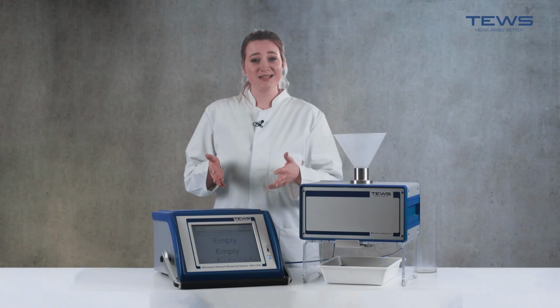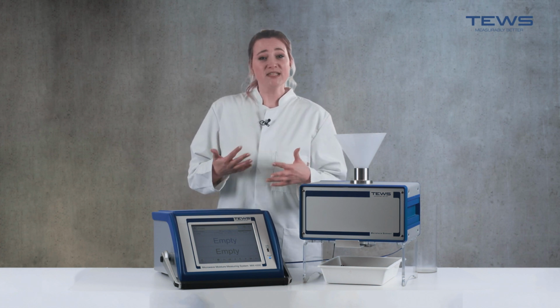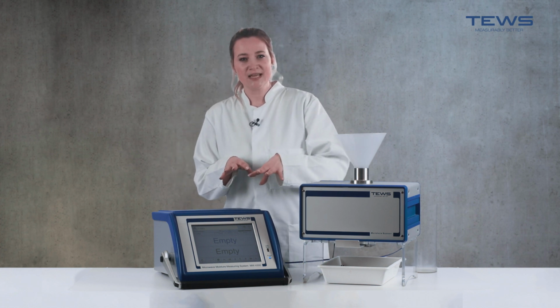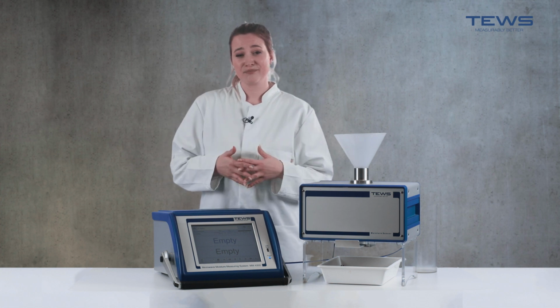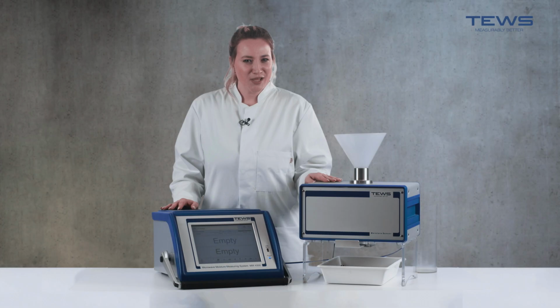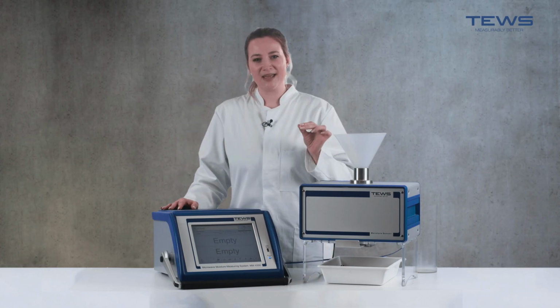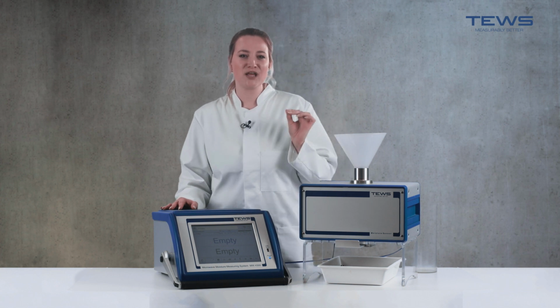We, on the other hand, can measure the moisture of the entire product. And this is because our frequency waves can penetrate further than just the surface. This is something NIR can't do. To be specific, our wavelength is 100,000 times longer than NIR, meaning we penetrate the product 100,000 times deeper.